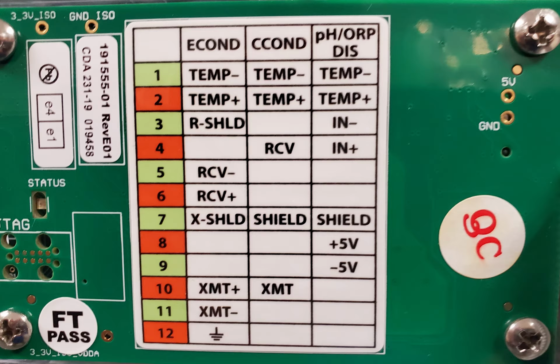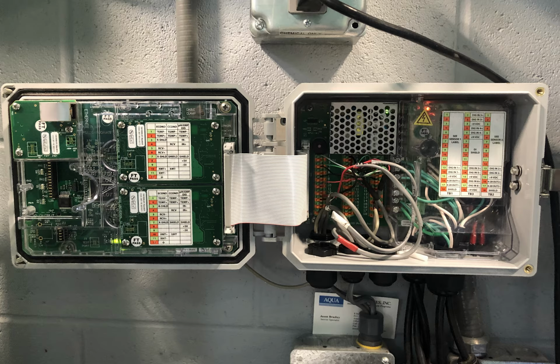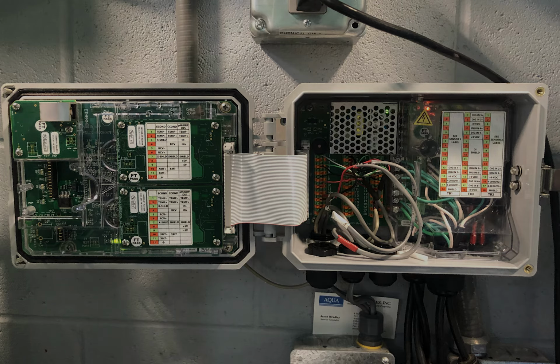The red wire on the sensor will get wired to the terminal block XMT. The black sensor wire gets wired to RCV, the green wire to Temp Plus, the white wire to Temp Minus, and the ground wire to Shield. If the sensor does not have automatic temperature control, it will only have 3 wires, red, black, and Shield. After wiring the boiler conductivity sensor to the controller, the user will now have to set up the sensor in the controller menu. In order to do that, you will need to do the following.